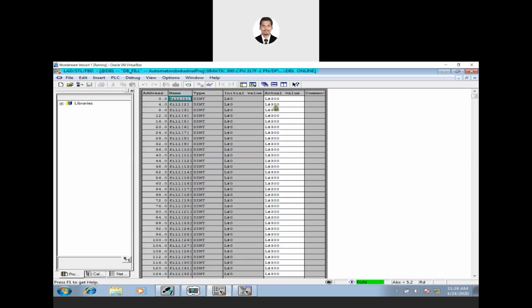In STL, while dealing with the DB, we have to open the DB and close the DB. Yes. In STL there is no concept of a for loop, but there is a concept of loop which you can use, and this loop works with the pointer address or with the address registers.